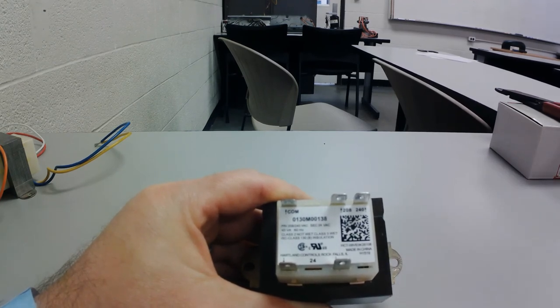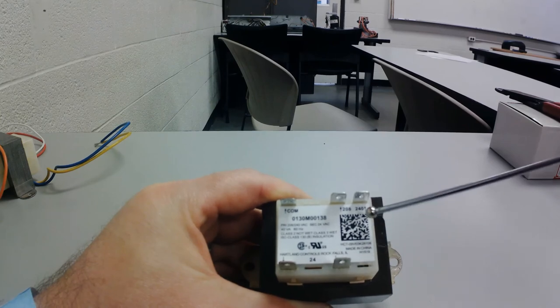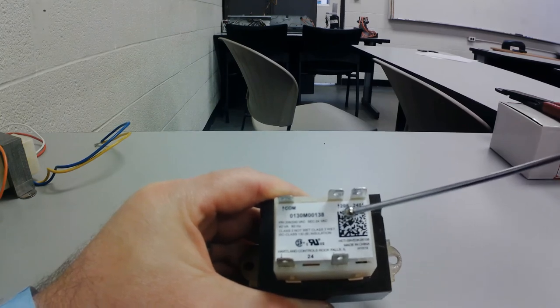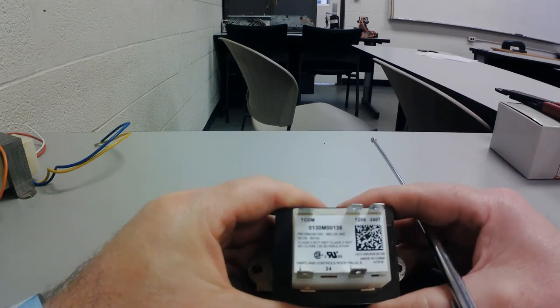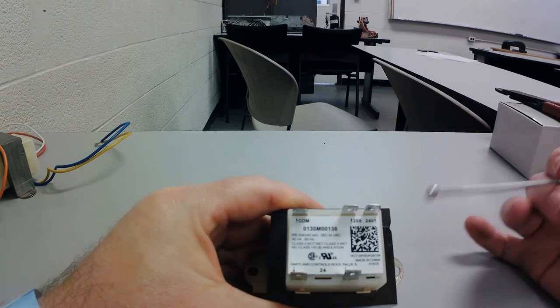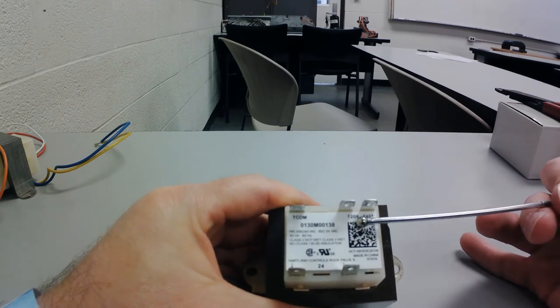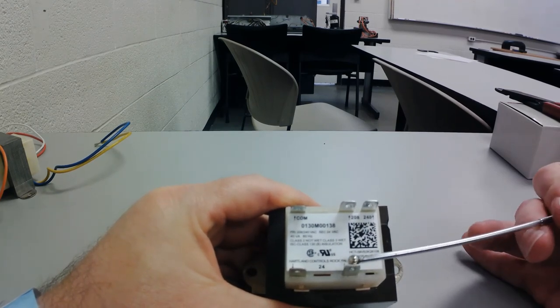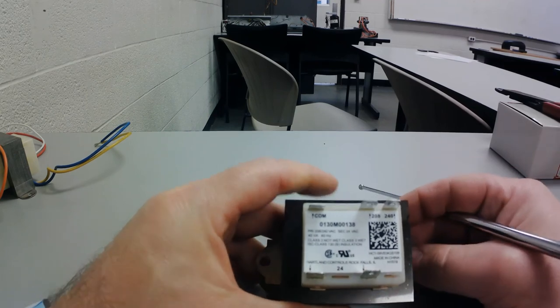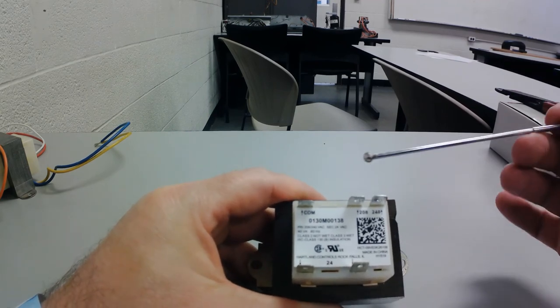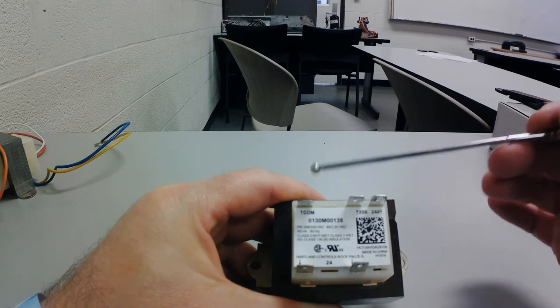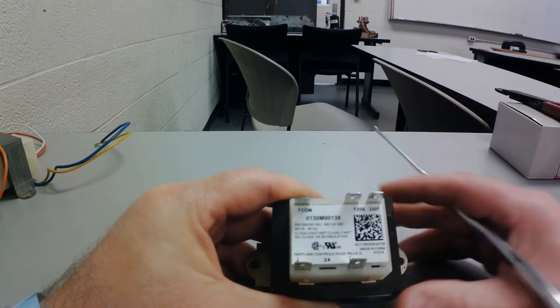The opposite is also true. What if I'm on a 240 power system, and I tap this on the 208 and common? You've put in more power than that 208. You put in 240. So you can expect your voltage to be higher than your 24 volt nominal voltage that you are going to see out there. You're going to wind up probably with 29 or 30 volts. And, you know, that's not good.